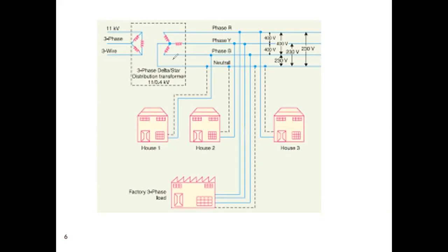And again we use the secondary distribution system. In the secondary distribution system, one transformer is placed, called a step down transformer. The primary winding is connected in a delta and the secondary winding is connected in a star connection, a star connection with four wire system.